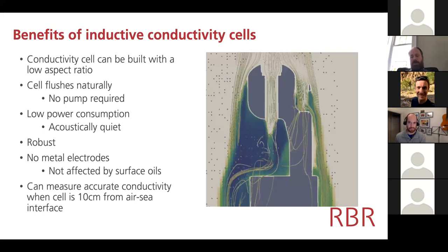The other thing that affects you in a CTD that you're going to bring up to the surface is that you often have contaminants in surface waters. They might be oils, they might be other material, and you want to make sure that the measurement is accurate in those surface waters. If you've got electrode-based cells, they get fouled very easily. Microscopic amounts of oil basically give you an egregious result on the data that you get back. And in the Deepwater Horizon case in the Gulf of Mexico, special cleaning instructions had to be given to people who had electrode-based conductivity cells.